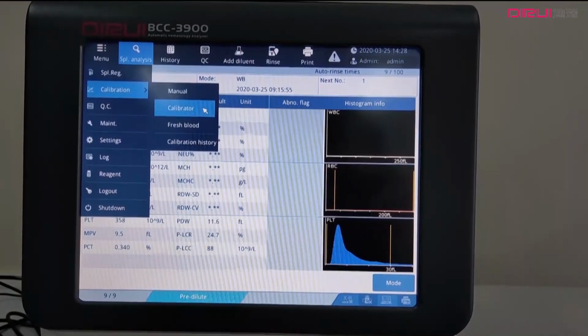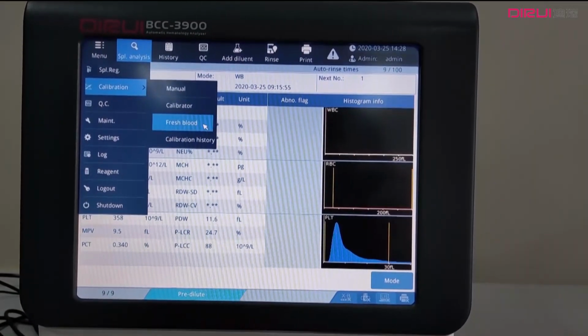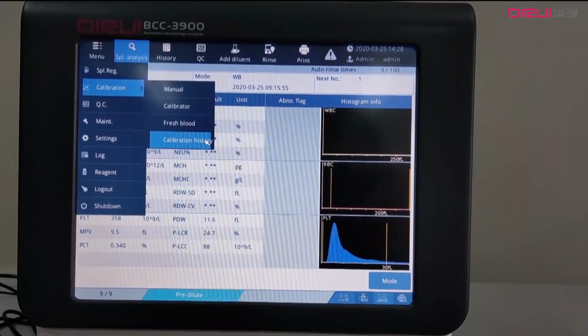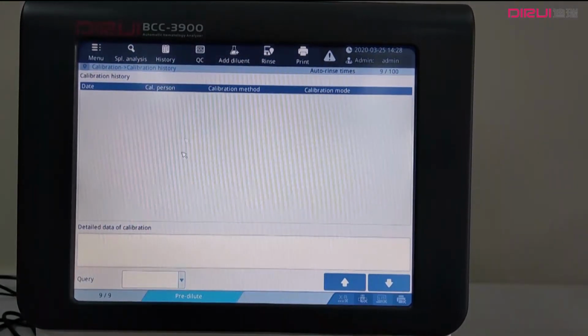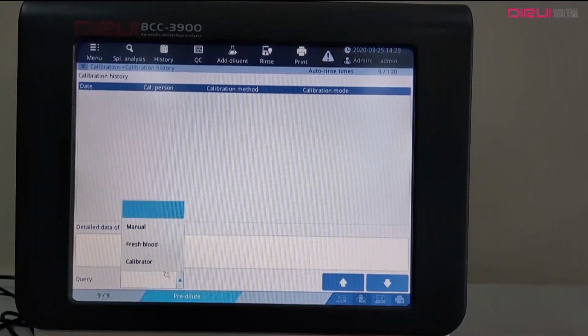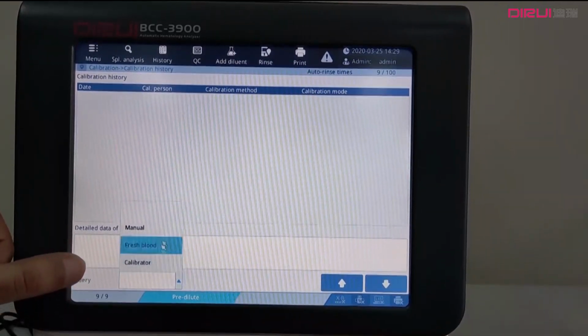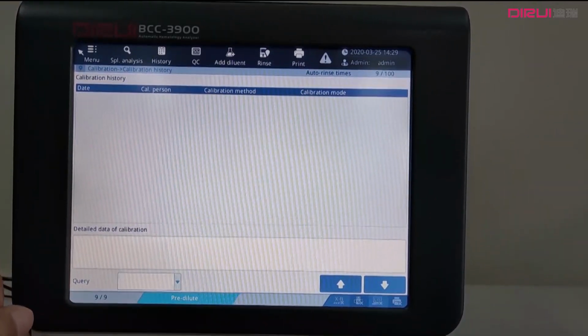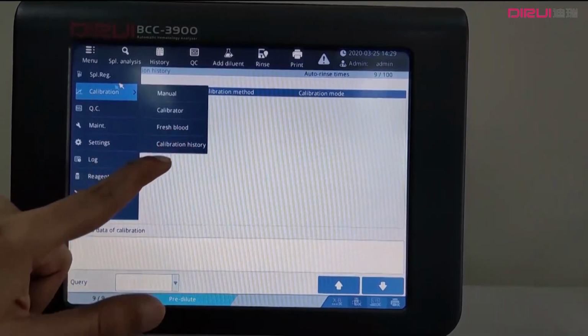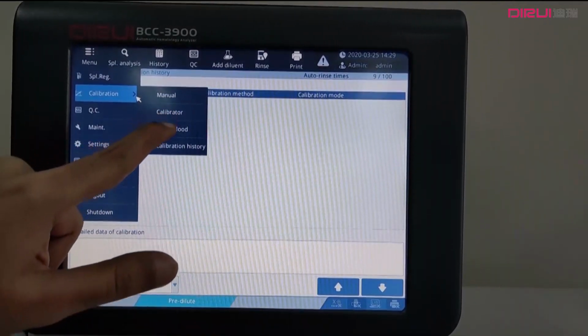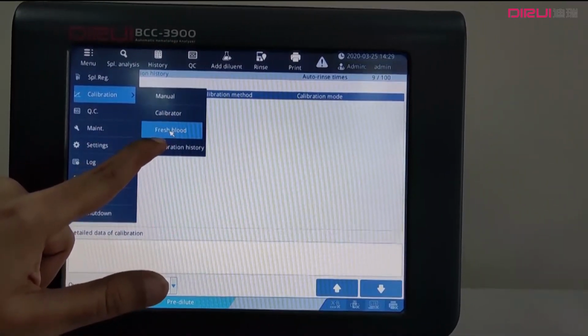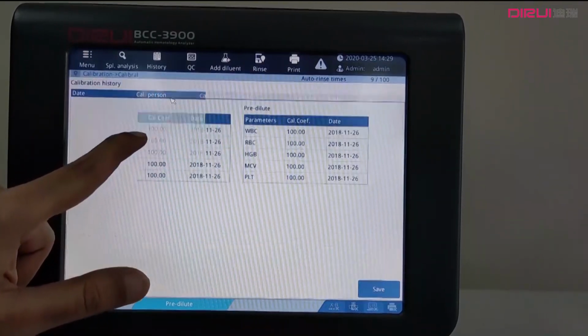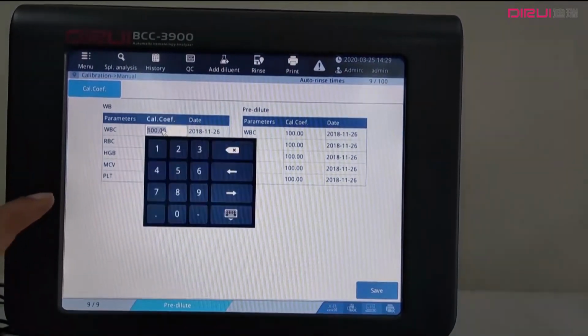After you have done the calibrator calibration and fresh blood calibration, you can check all of the history from calibration history, and from the query tab you can check fresh blood or calibrator or manual. The difference between history, calibration history and manual is that the results of calibrator and fresh blood will be shown in manual, and here you can edit the results.